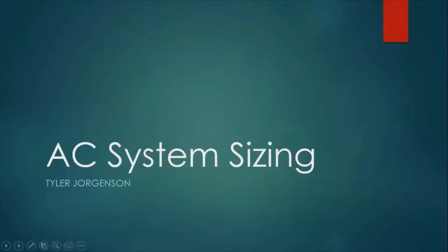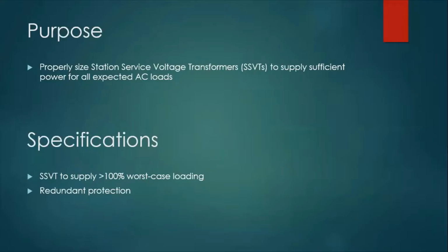I'll be discussing the AC system sizing study for the Jackrabbit substation. The purpose of this study was to properly size station service voltage transformers, SSVTs, which are line to ground, single-phase transformers that step down high voltages to the usable level to supply AC loads. The specification was that each SSVT set had the ability to supply more than 100% of the worst case expected loading while maintaining redundant protection.